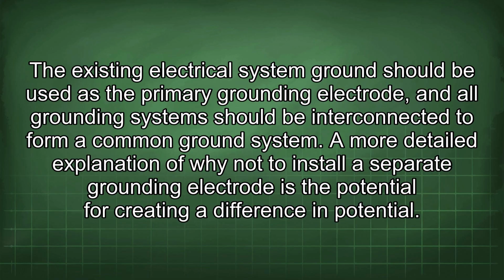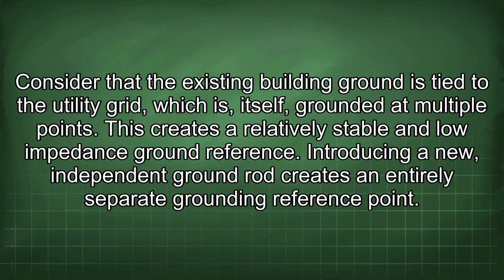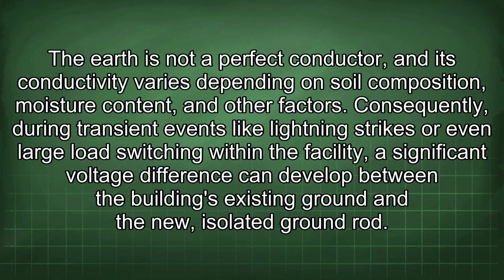A more detailed explanation of why not to install a separate grounding electrode is the potential for creating a difference in potential. Consider that the existing building ground is tied to the utility grid, which is itself grounded at multiple points. This creates a relatively stable and low impedance ground reference. Introducing a new, independent ground rod creates an entirely separate grounding reference point. The earth is not a perfect conductor, and its conductivity varies depending on soil composition, moisture content, and other factors. Consequently, during transient events like lightning strikes or even large load switching within the facility, a significant voltage difference can develop between the building's existing ground and the new, isolated ground rod.